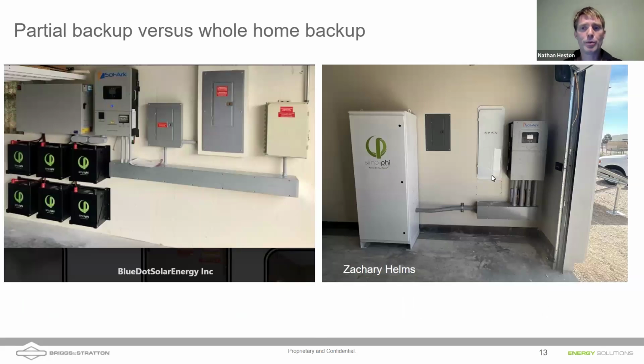Here are a couple of examples. On the left side of the screen, we're looking at a nice looking install. It's got 6 SimpliPhi batteries. It looks like a Sol-Ark 12k, and you can see a critical loads panel closer to the inverter. The big box in the top left looks like a DC combiner box with a breaker on it. And then on the right side, you have the main loads panel to the house. So any loads left in this main loads panel will not be backed up, only ones in the critical loads panel.